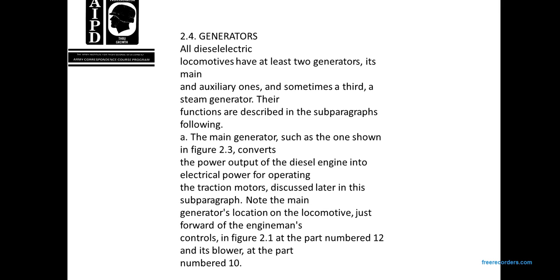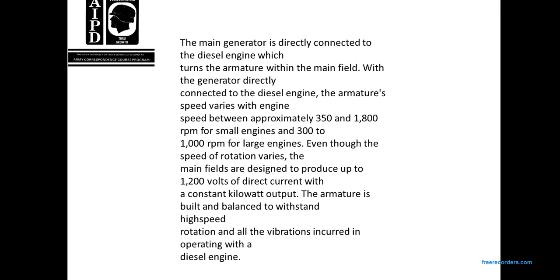In Figure 2.1, part number 12 is the generator and part number 10 is the blower. The main generator is directly connected with the diesel engine and turns the armature with the main field. With the generator directly connected to the diesel engine, the armature speed varies. The engine speed is approximately 350 to 1800 RPM for a small engine, and 300 to 1000 RPM for a large engine. Even though the speed of rotation varies, the main fields are designed to produce up to 1200 volts of direct current for a constant kilowatt output. The armature is built and balanced to withstand the high-speed rotation and all vibrations incurred in operating with the diesel engine.